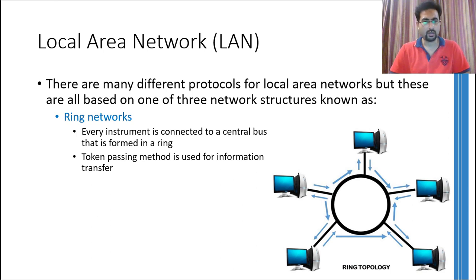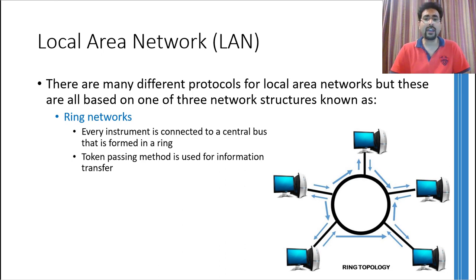The last type of architecture is called the ring network. The network got its name from the way the devices are connected — all devices are connected to a central circular bus and can communicate with each other directly. To limit traffic or avoid any collision between data packets, token passing method is normally employed. The token passing method gives a token to a particular device, and if that device has to communicate something, it can communicate while it has the token. After a particular time, the token moves to the next device. This ensures that no two devices can send data at the same time on the bus, hence avoiding any kind of collision and contention.